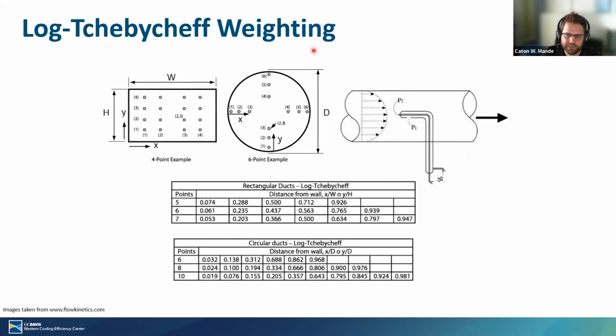And taking these measurements is what's required to get an accurate velocity profile for the duct so that you can then convert that into an accurate volume flow. So if you think about this, if you're trying to just verify the measurement in the simple example that I showed you, it's not just a one and done type scenario. You're having to take some fairly precise measurements, with a handheld tool, and then some post-processing to get the result that you want.